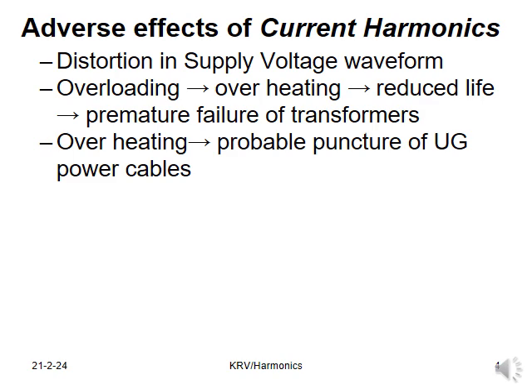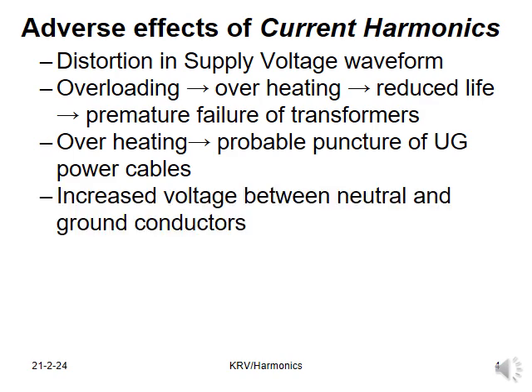Ideally, in a UG power cable distribution system where 3.5 core is practiced, the neutral conductor will not carry any current. But if harmonics are present, there will be a significant amount of current in the neutral conductor, which causes more heating and probably the UG power cable punctures. Increased voltage between neutral and ground conductors, which otherwise ideally should have been zero or very minimal.